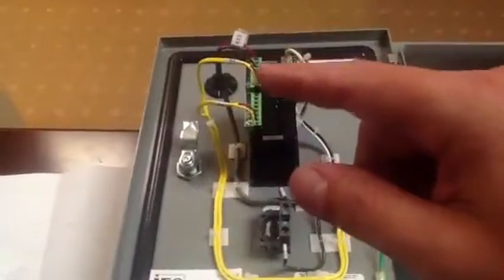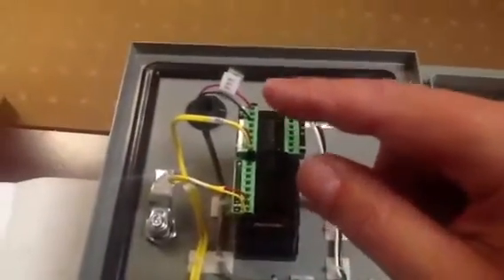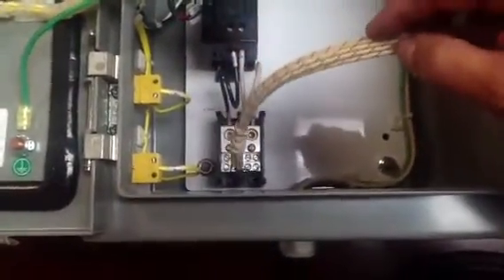We've got the two sensors that are coming in from the outside. They're coming up. One is for control of the heating system, and the other one is for the part temperature. The output of the heater is actually going over to the solid-state relay, which turns on and off to allow power to flow out to this terminal block where all the heaters themselves, so here are the heaters. They will be connected through a conduit to this terminal block on the backside.